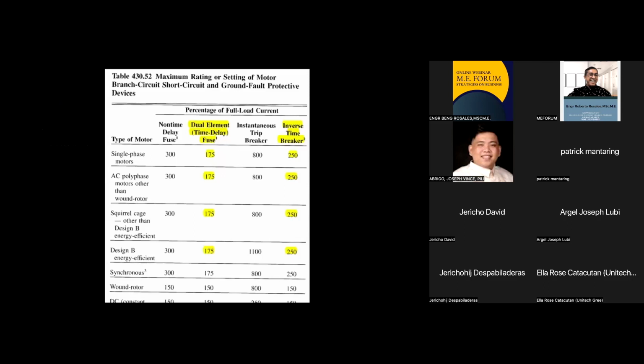Now, this is what I was talking about. This is based on the National Electrical Code, a US-based criteria, for what our protection multiplier is. If you look at it, we use 1.75 here at Unitech. The most is 2.5. Most of the time, current multipliers are only between 1.75 and 2.5. It won't go higher than that range. If you multiply within that range, the system is okay. It won't flip.